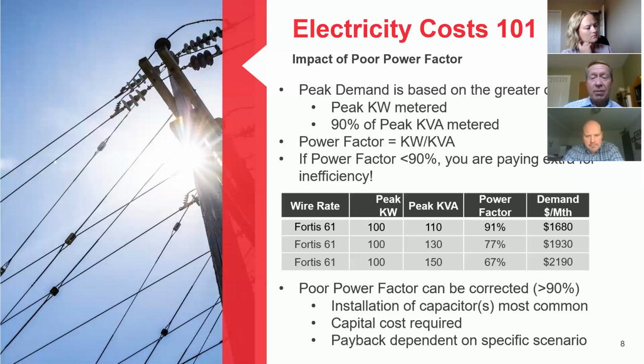So power factor can be improved in an operation or in a customer's site in a number of ways. The most common way is through the addition of capacitors that store and provide energy when needed, which reduces the kVA required from the wire's provider. The options to improve power factor are actually fairly widely varied, but they're very specific to each site scenario, and they generally require upfront costs to fix the issue. So payback is really dependent on the scenario, and it may not make sense in all cases, but it's definitely something you should take a look at if your power factor is below 90%.